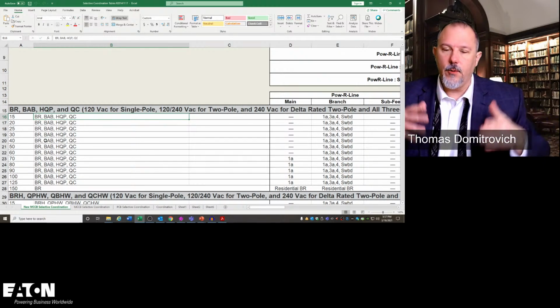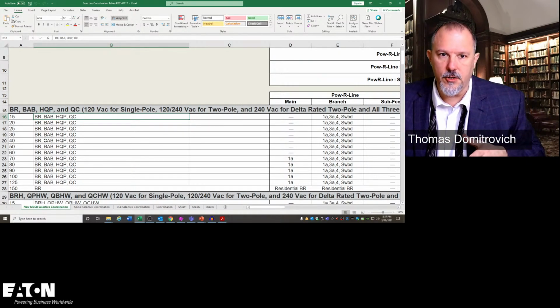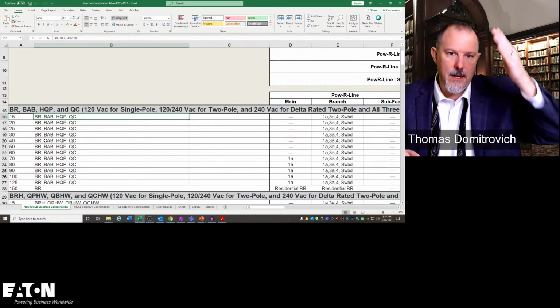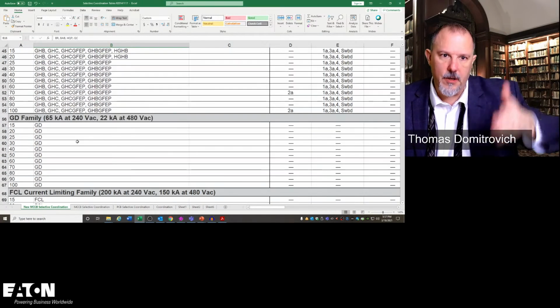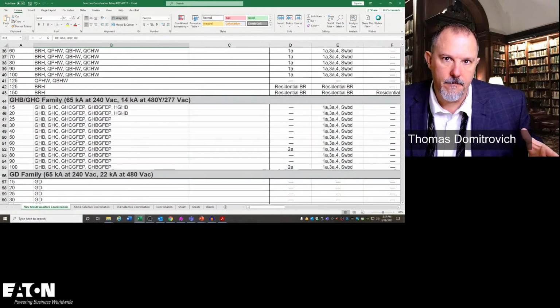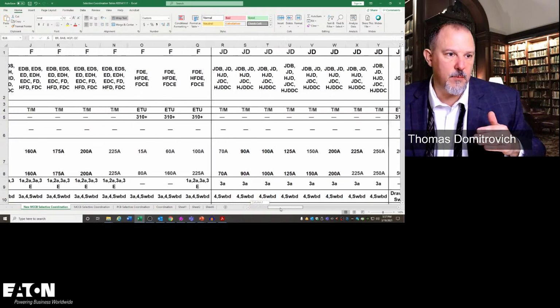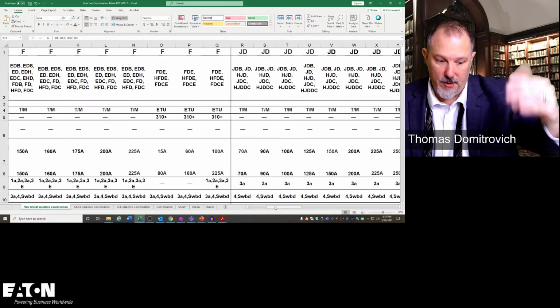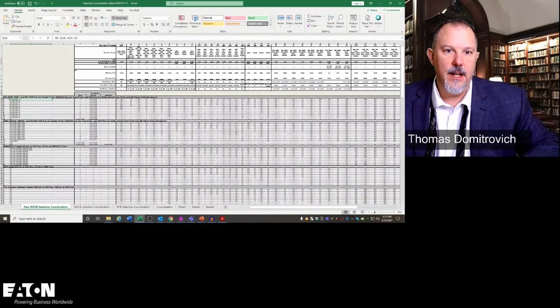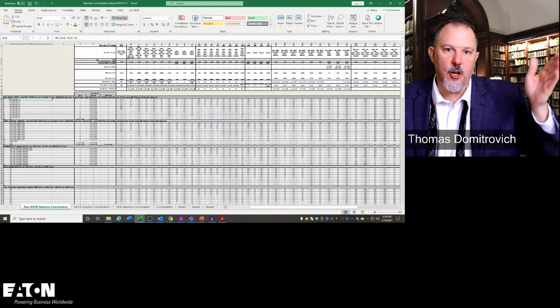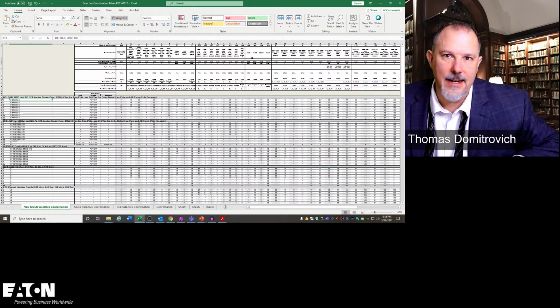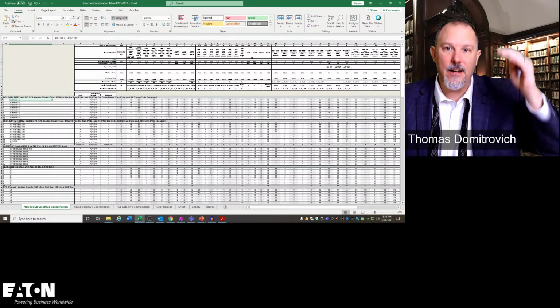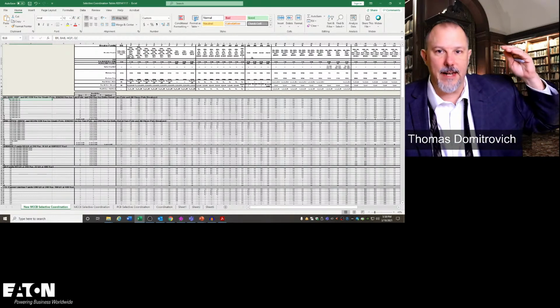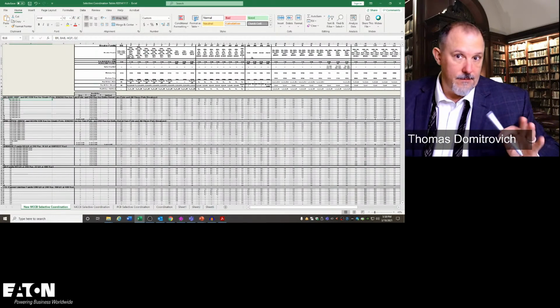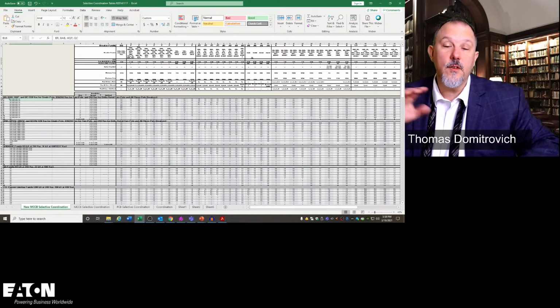And I'm going to tell you how we do it, which is a little different than what our competitors do. Down the side of this spreadsheet is my downstream breaker. Across the top of this spreadsheet is my upstream circuit breaker. So if I zoomed out on this, down the left-hand side is my downstream device. Across the top is my upstream device. Makes sense, does it? I don't know why everybody else does it just the opposite. If you go to some other manufacturers, they put the downstream breaker across the top and the upstream breaker down the left-hand side. I'm just saying why you filter on Eaton.